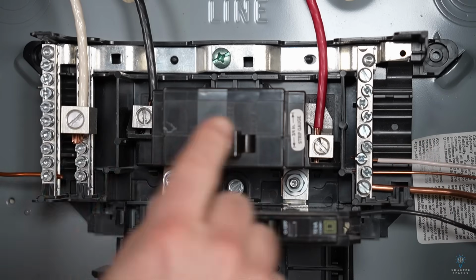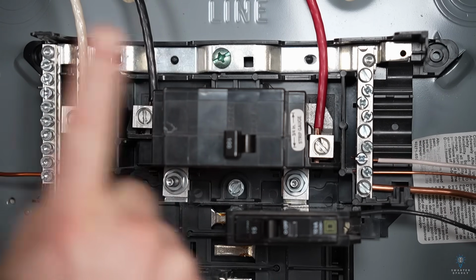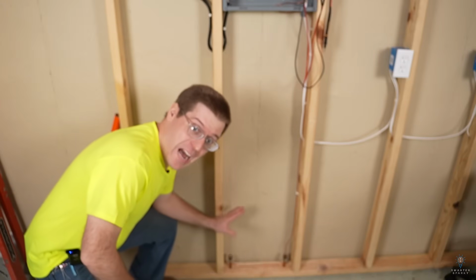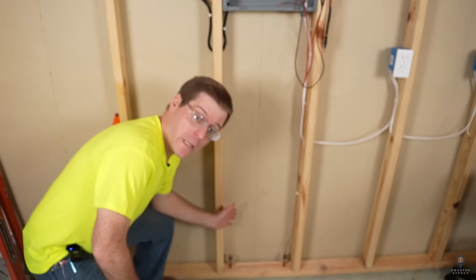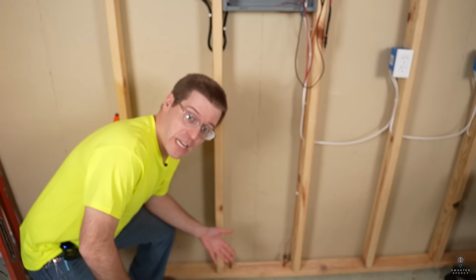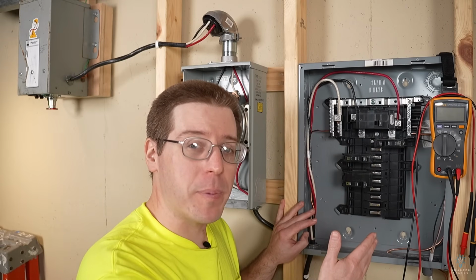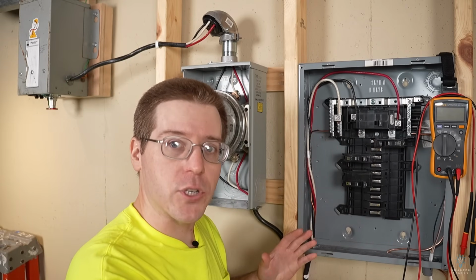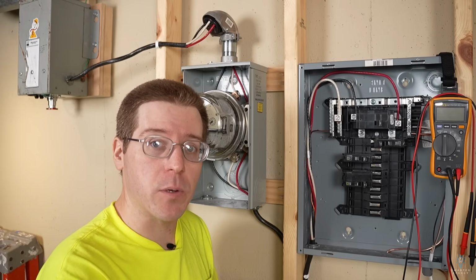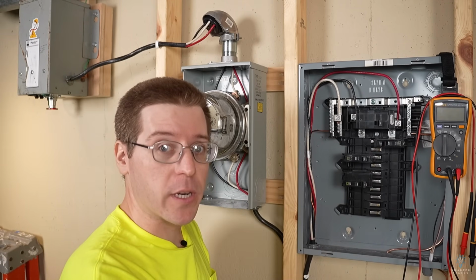In the main panel, the neutral and ground are bonded together through the main bonding jumper. In sub-panels, they have to remain isolated. And the ground rods are not there to trip a breaker. They are only a voltage reference. The only time they do anything is in the event of a lightning strike or a surge. Hopefully this video has made what's inside of a main electrical panel less random and more logical. In future videos, we'll dive deeper into topics such as how split phase actually works, grounding and bonding in more detail, and specific branch circuit applications.